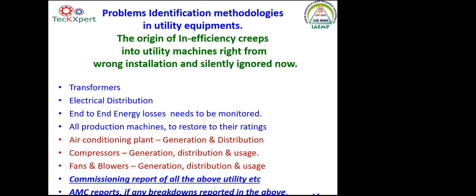For the fans and blowers also, everyone thinks it is only generation, distribution, and usage. In fact, in many of the waste collection mechanisms in our industries, we have seen leakage, where in some places the equipment is kept open. That means it is a leakage. Air is getting sucked in from the atmosphere. It is a redundant use of the blower for atmospheric air. It is not being used for the purpose of the machine, but is taking air from outside. It is a loss for the blower's efficiency.